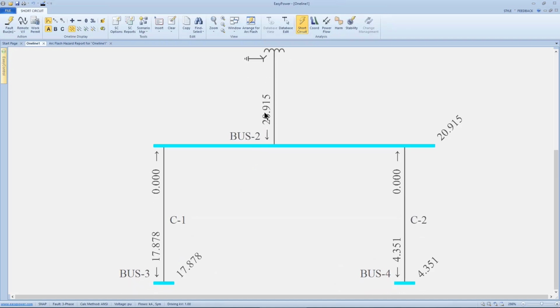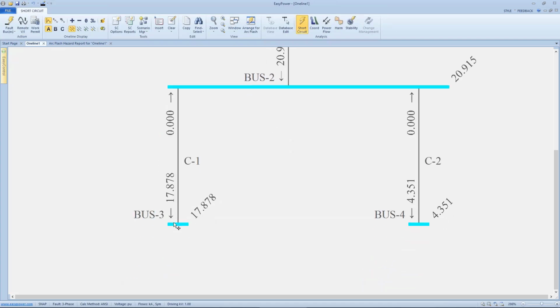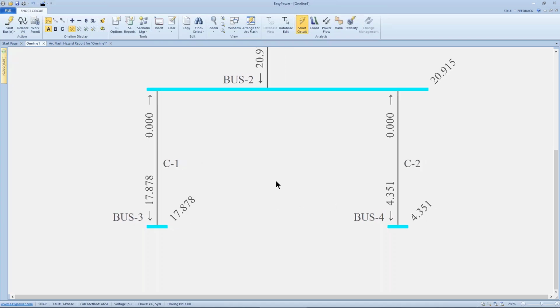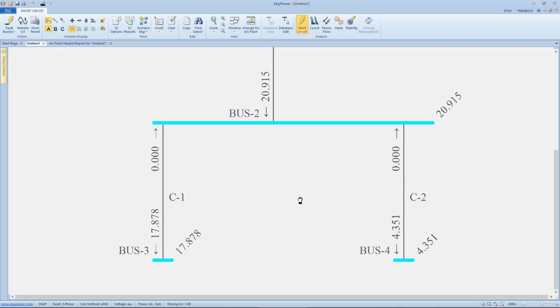He says, Jim, I understand this is looking at the A phase. If we look at the B and C, they're all equal because it's a balanced fault by definition. But this indicates if we have a bolted fault on bus 2, each phase will see 20,915 amps coming from the transformer. If we have a bolted fault on bus 3, we'll see 17,878 amps per phase coming from upstream. He was disregarding the downhole motors, which would be a load on his system, which was fine with me. And he says if we have a three-phase bolted fault on bus 4, each phase will see 4,351 amps. He says, okay, that makes sense.